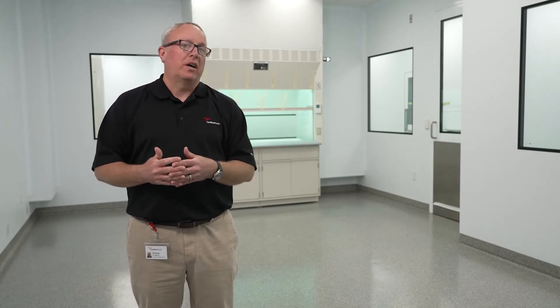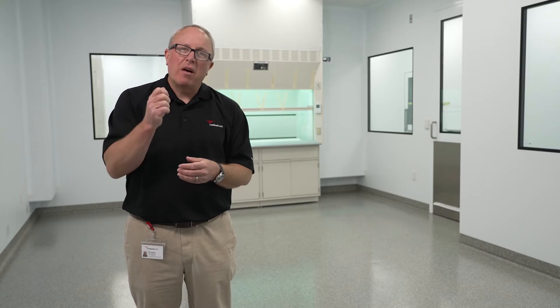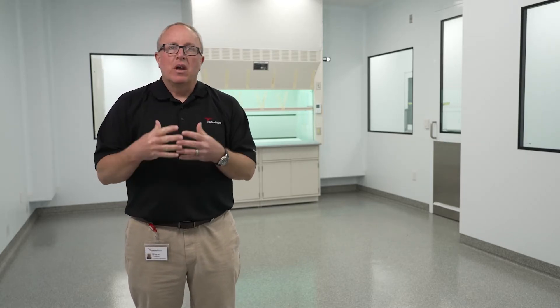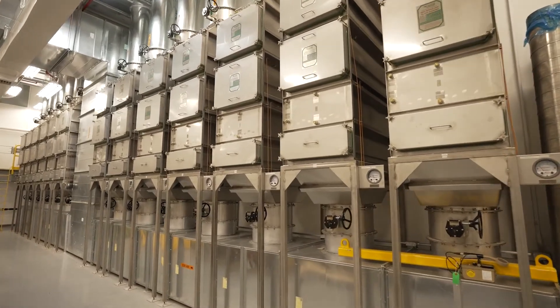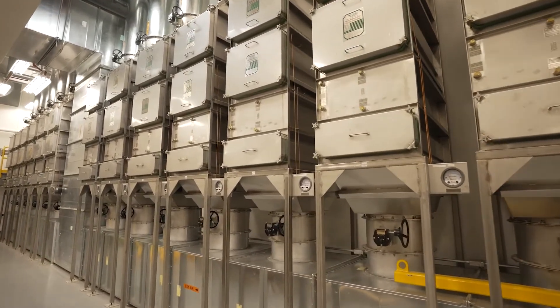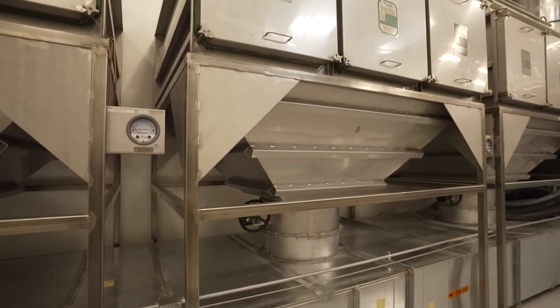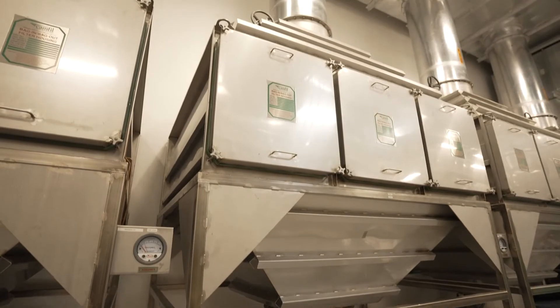All this provides a unique flexibility for multi-process manufacturing — that really is the unique differentiator for us. Here in the pre-commercial manufacturing center, a unique and extensive air exhaust capability exists that includes HEPA filters, charcoal scrubbers, and an extended plenum capable of a nine-minute decay dwell for isotopes like radon 220.